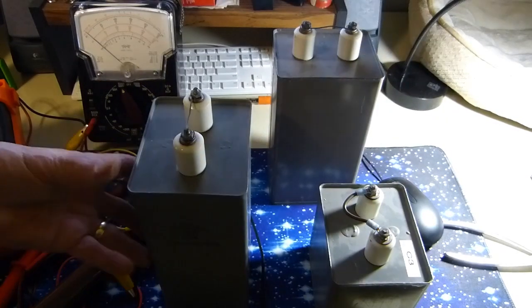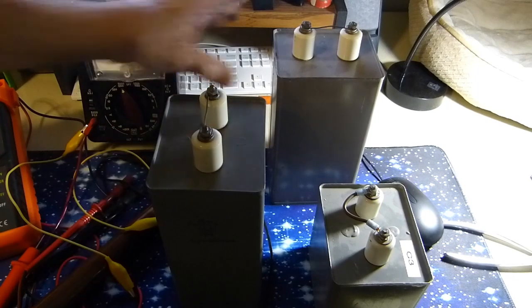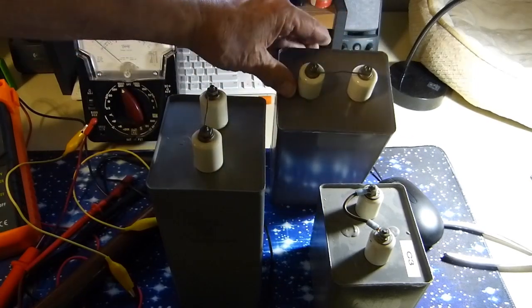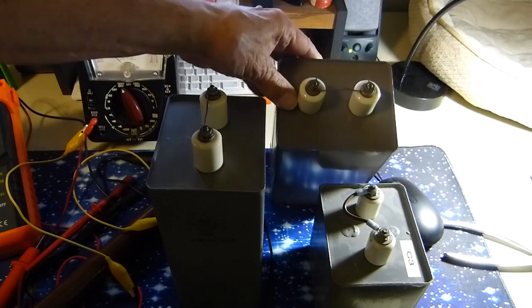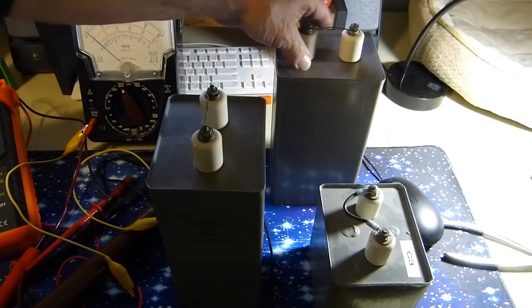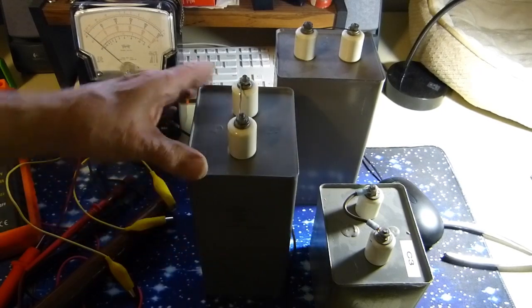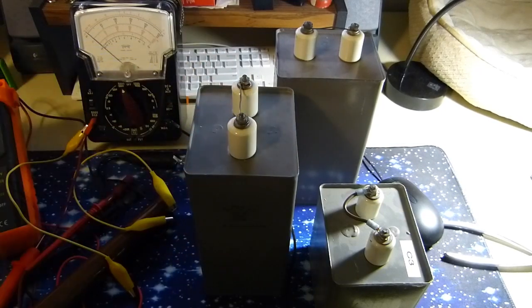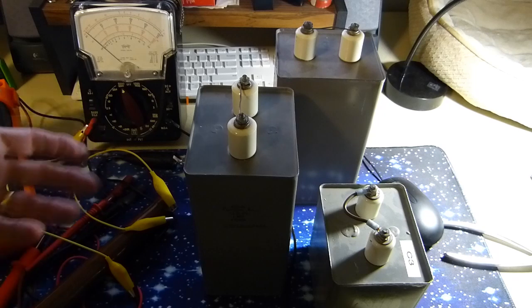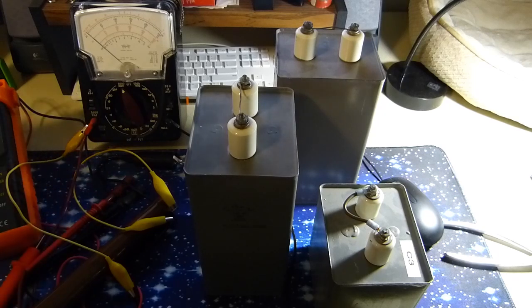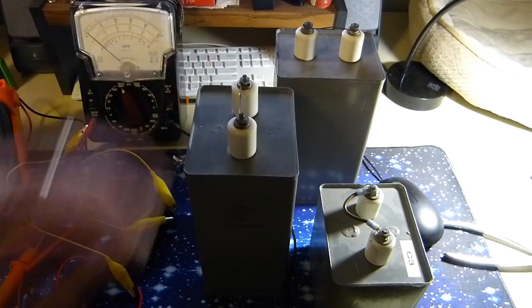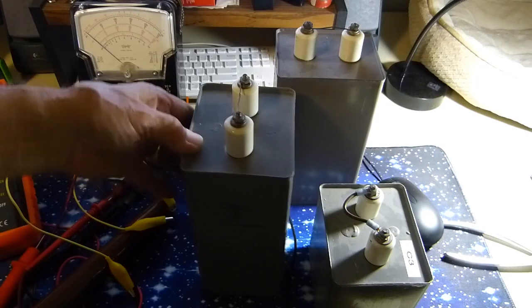Also, when you have capacitors like this just hanging around stored, you always want to keep them shorted, because I've seen this happen. I've had capacitors like this, maybe not these particular ones, that sat around without a shorting bar for a year or two, some great length of time. I wondered if there was really a charge on there, and you can take a voltmeter and stick it on there. It's probably not going to be 5 kilovolts, but it could be 1 or 200 volts. I don't remember the exact number, but you can measure a little voltage across them, then short them and get a little spark, just because these things are so darn good.